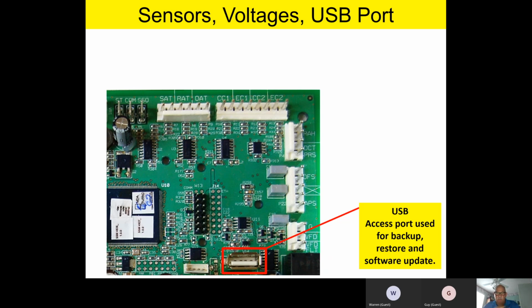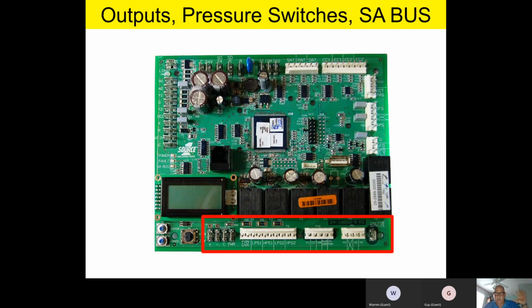All right, let's take a look at the bottom of the board in our photo. We're going to blow that up and talk about it. If you take a look at this board, you're going to notice there's a whole bunch of relays right above where we're talking about. Those are the relays I'm talking about. This board that you're looking at right here is probably a replacement board that I got for purposes of training. Your actual board from the factory may have fewer relays. It might be a dedicated single-stage board or whatever. But if you have a replacement board, it's going to look like this one, where it's got all those relays down on the bottom, and it's a universal board that'll work fine on any of the equipment. So what we're looking at is a replacement board, in answer to that good previous question.